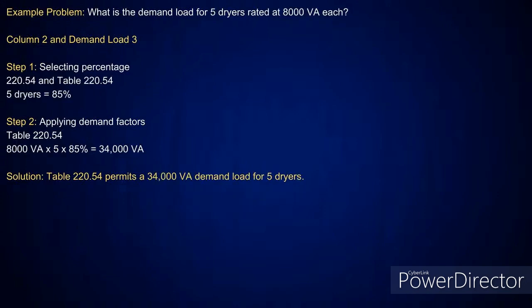Well, here's one. I'm going to show one where I have 5 dryers. And each one of them are 8,000 VA each. So it exceeds the 5,000 VA. Now, if I look in table 220.54 and I pick up 5 dryers, what does it tell me take it at? 85%. Yeah. So I'll just take the 8,000 times my 5 dryers, take it at 85%, and it's going to tell you the VA load there's 34,000 VA. All right. Very simple. Cool.